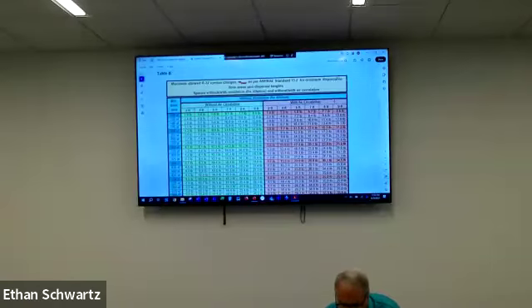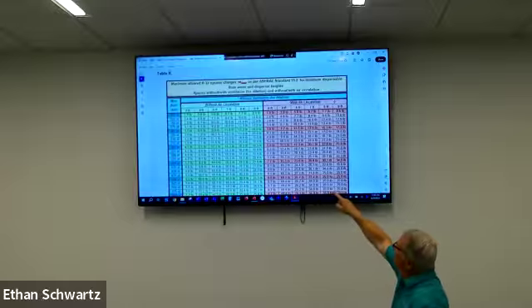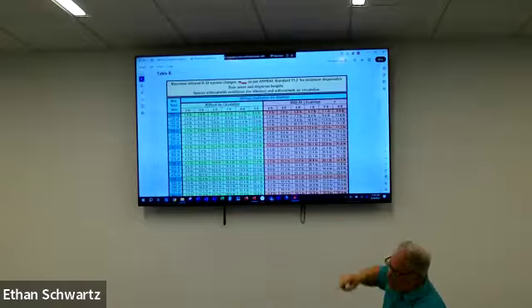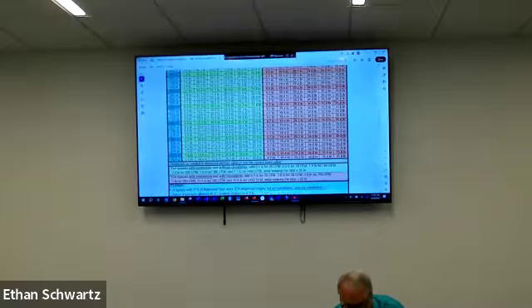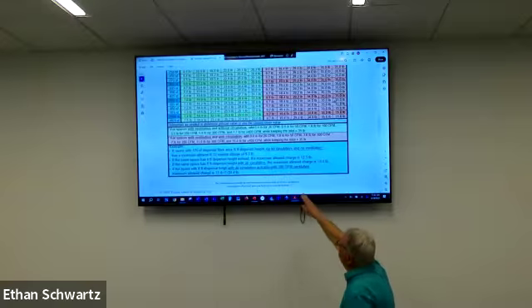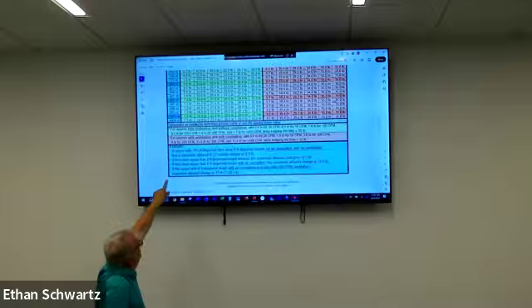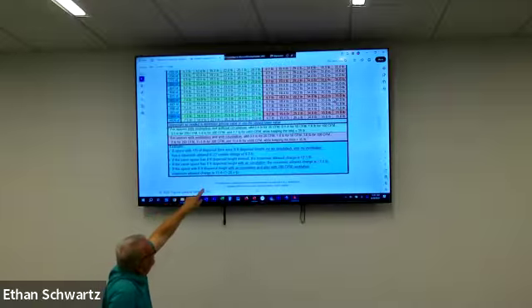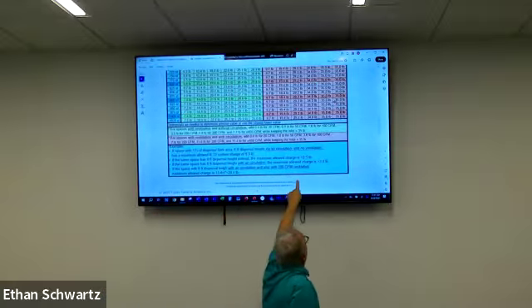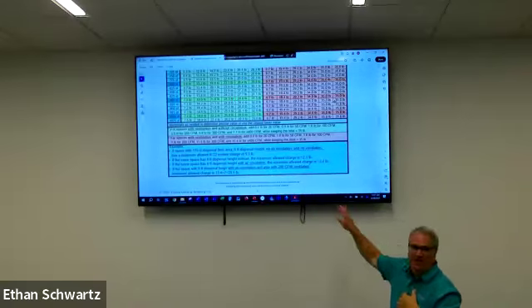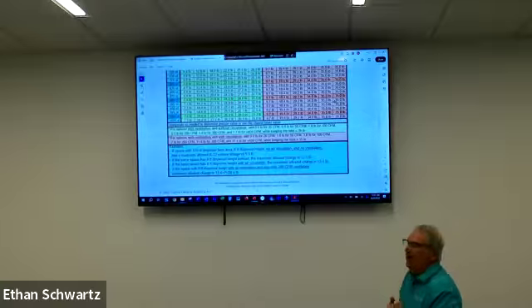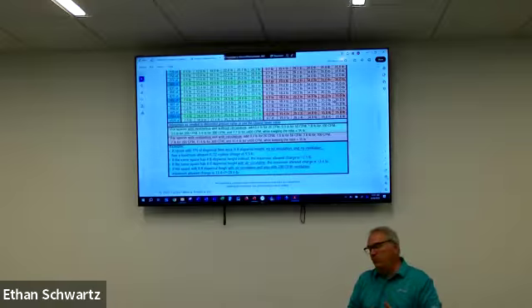But if you add in, and that's what the top says, spaces with or without ventilation or dilution, and with and without circulation. So we scroll down here through all these different sizes, and you see for spaces with ventilation but without circulation, add 0.4 of a pound for 20 CFM of ventilation, 0.9 of a pound for 50, 1.8 for 100, and so on. Everybody see that? So that's why, yeah, I think going forward, even more than just having good indoor air quality in a structure, you're going to want to kind of brush up on what are my ERV products? What do I have available?